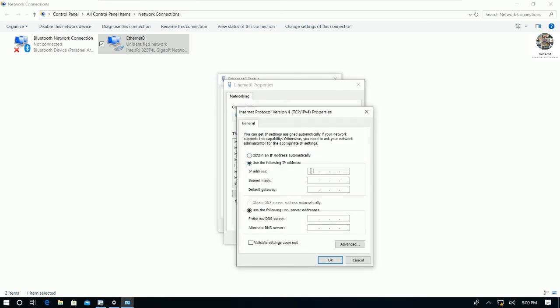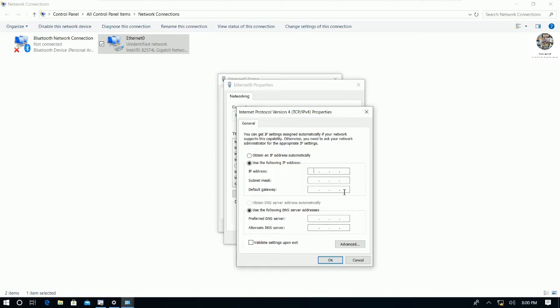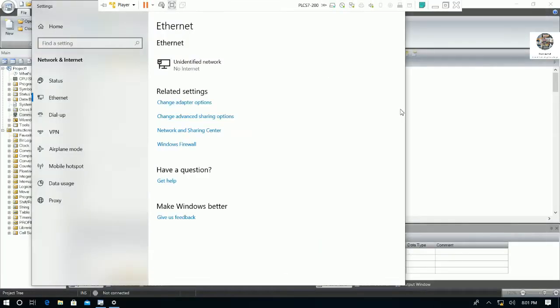We can set the IP address manually as mentioned. The IP address of the PLC is 192.168.2.2 and the IP address of our computer will be 192.168.2.253. For the subnet mask we put 255.255.255.0 — we call it Class C. Then click OK, OK again, and close.